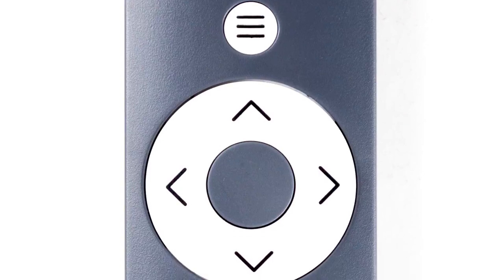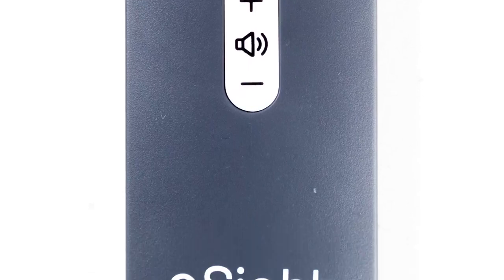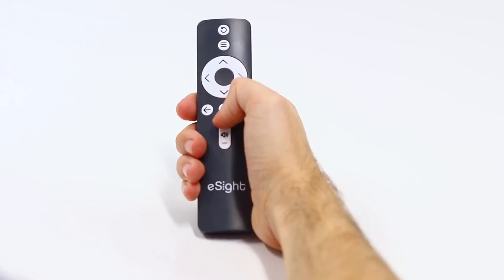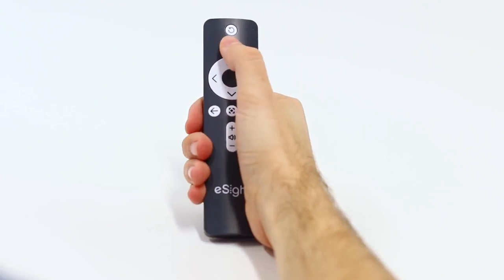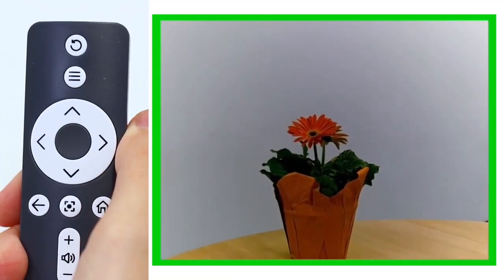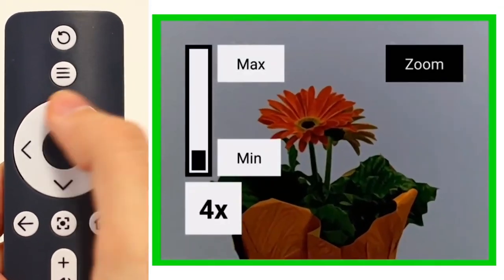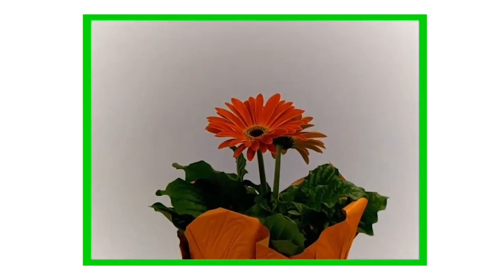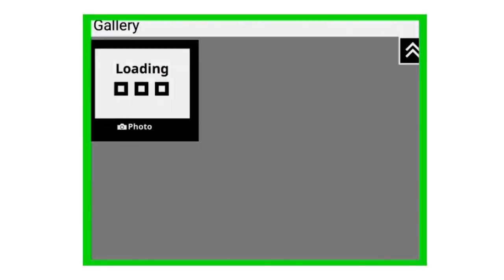Next, let's use the Bluetooth wireless remote. Using the remote, users can access all the vision controls integrated in the headset and also adjust the voice narration volume. They can press the reset view button, helpful for new users learning to navigate the software. They can choose freeze frame to pause the camera image at any time, and when an image is frozen, use zoom and contrast to see it in fine detail. They can also take a picture, record video, and access their photos and videos in gallery view.